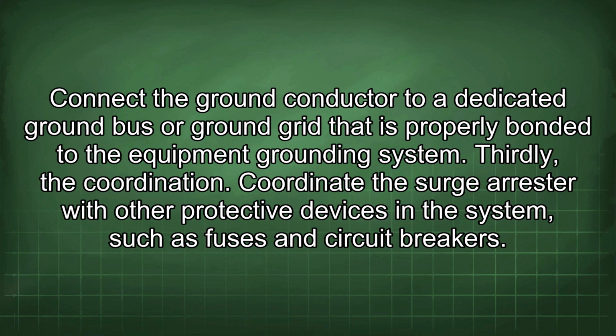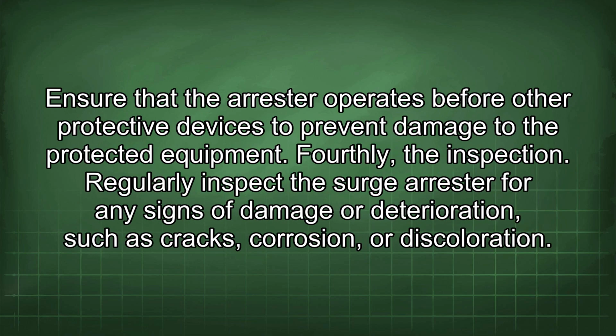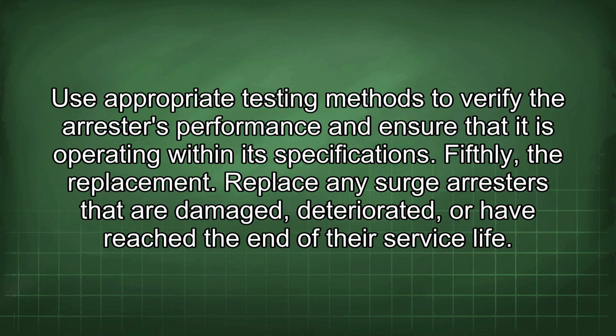Thirdly, the coordination. Coordinate the surge arrestor with other protective devices in the system, such as fuses and circuit breakers. Ensure that the arrestor operates before other protective devices to prevent damage to the protected equipment. Fourthly, the inspection. Regularly inspect the surge arrestor for any signs of damage or deterioration, such as cracks, corrosion, or discoloration. Use appropriate testing methods to verify the arrestor's performance and ensure that it is operating within its specifications.